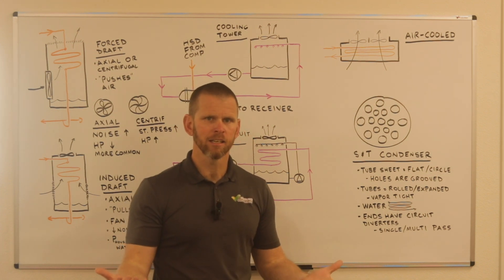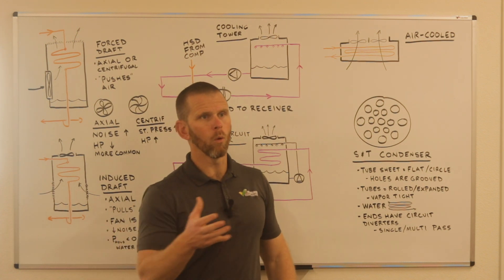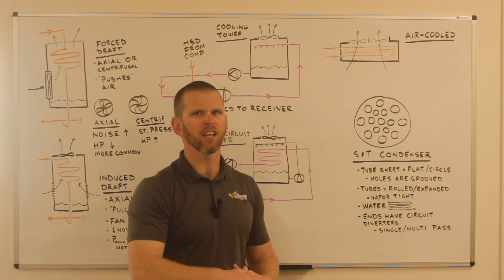You can have a single pass shell and tube heat exchanger in which the water flows through one time and exits on the other end. That's not the most common. You have a two pass where the water's diverting through half the tube, and then it comes back through.